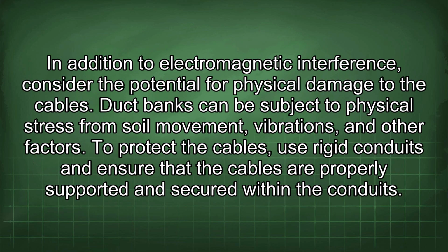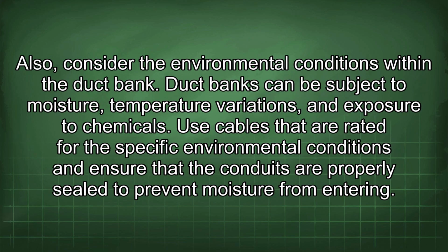In addition to electromagnetic interference, consider the potential for physical damage to the cables. Duct banks can be subject to physical stress from soil movement, vibrations, and other factors. To protect the cables, use rigid conduits and ensure that the cables are properly supported and secured within the conduits. Also, consider the environmental conditions within the duct bank. Duct banks can be subject to moisture, temperature variations, and exposure to chemicals. Use cables that are rated for the specific environmental conditions and ensure that the conduits are properly sealed to prevent moisture from entering.